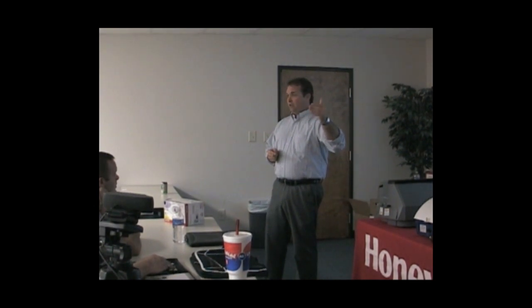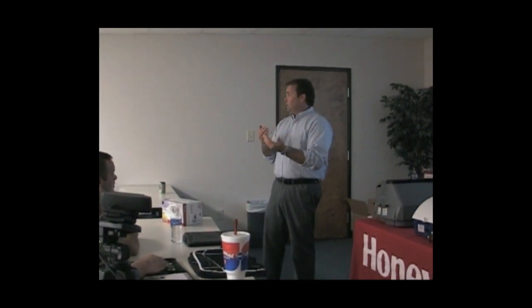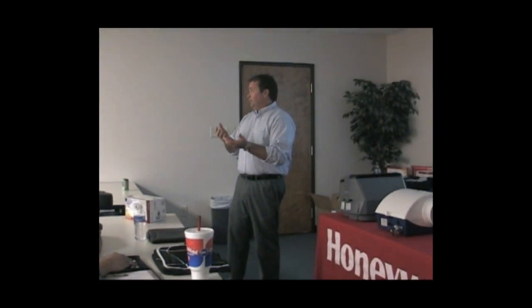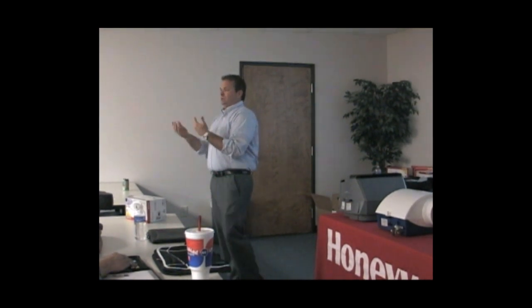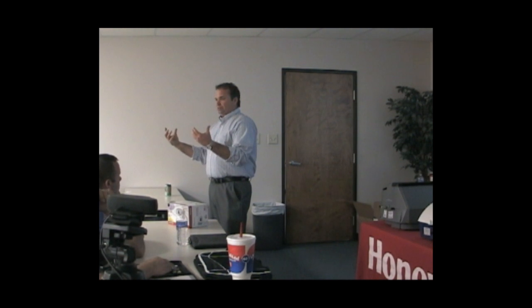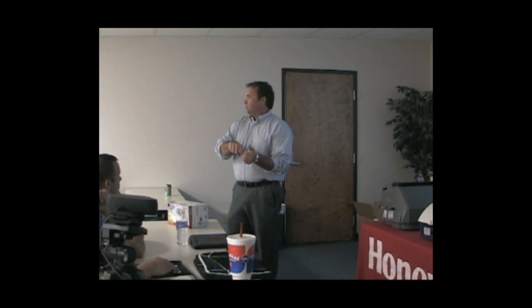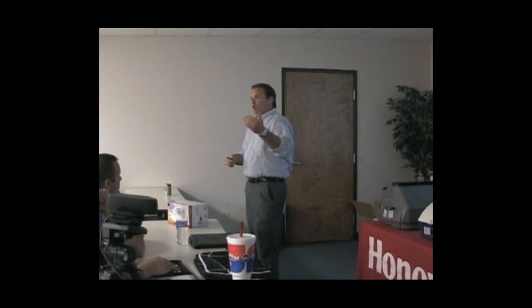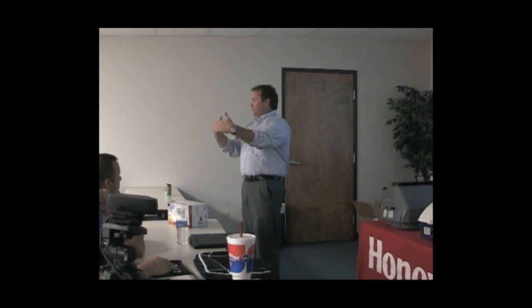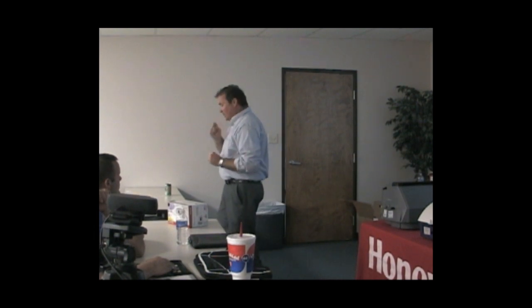In stage, each individual—first stage, second stage, third stage, fourth stage—a lot of people don't like the P+I control. Well, not a lot, 2 or 3 people a year will say, hey, this thing's keeping it too perfect in here. I'm like, what? That's the idea, we're trying to keep it plus or minus 1 degree. All of our thermostats are made with a P+I control, which is 2 different errors. It's like I got my GPS set—I'm going to Louisville tonight, and if I take a wrong turn, what does your GPS say? Recalculating, right? Front door opens, we're recalculating. We're trying to keep it plus or minus 1 degree, we may bump it up to second stage until we can drop it back down to first. So we're trying to keep it plus or minus 1 degree at all times.